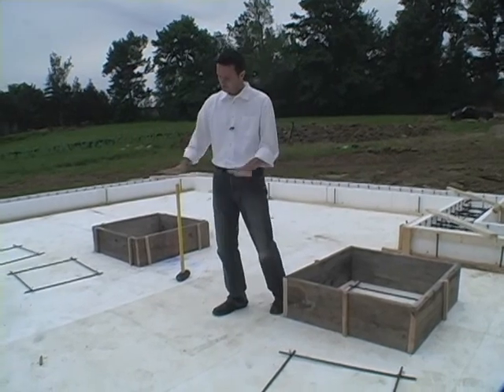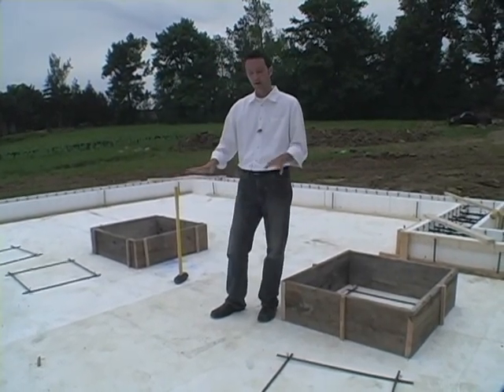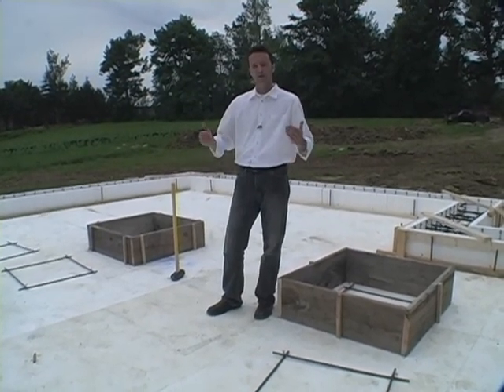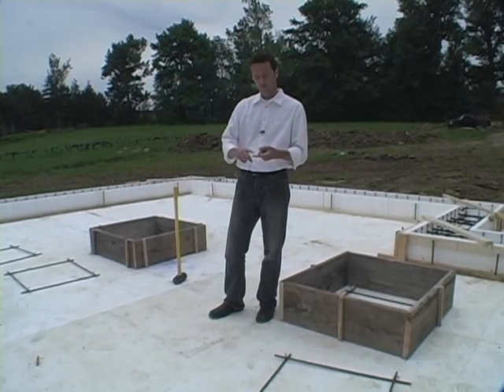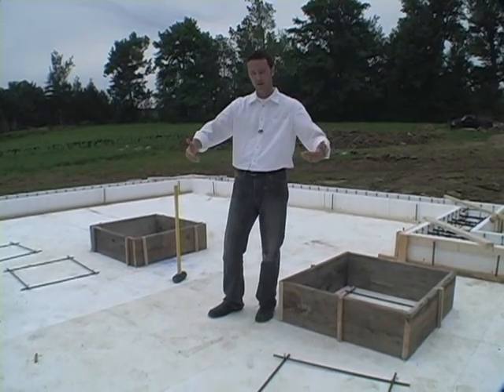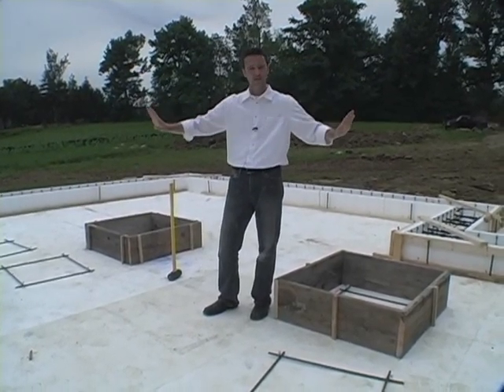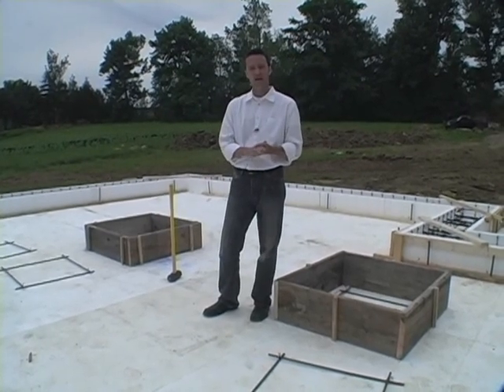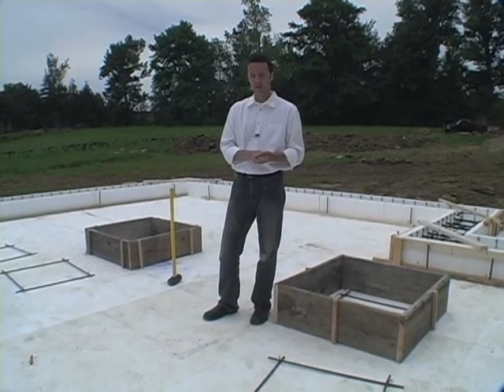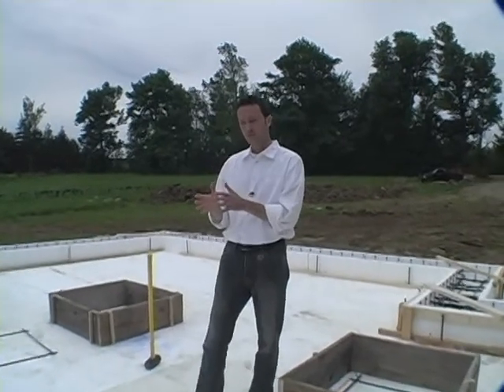So we're going to add rigid insulation, and underneath that rigid insulation, a very important thing happens. We're going to add a layer of plastic, which becomes a vapor barrier to the house. The reason we have the vapor barrier is twofold. One is for moisture control, but also air infiltration. And we'll take that vapor barrier and air barrier and run it up and attach it to all the walls and seal all the walls, because what's critical in the high-performance house is to control the unintended airflow or infiltration in and out of the house. It's important to make sure that we don't get any cold air from the exterior that's unwanted and not controlled. And as I mentioned earlier, we have a heat recovery ventilation system to provide the healthy indoor air environment.